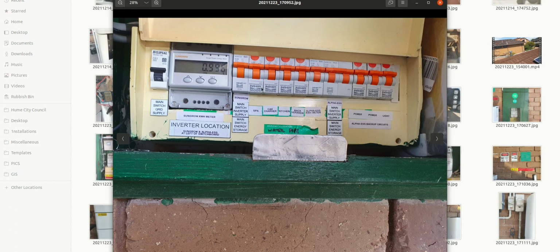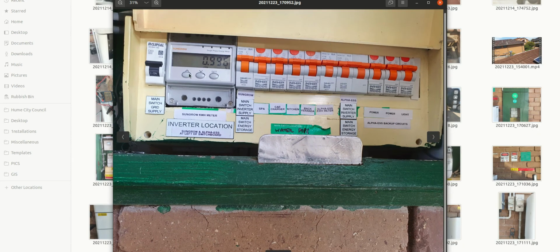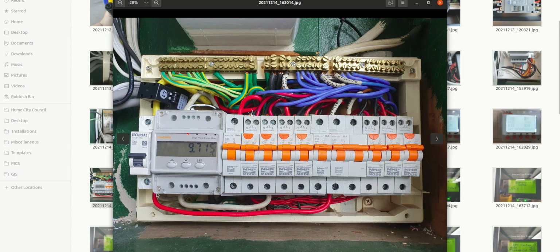These are grid connect. So when you had, yeah, that's right. This kilowatt hour meter here is grid side, and the Alpha ESS has its own backup circuits. And this kilowatt hour meter here from this retro system can't recognize any other system. So the answer was to, I have to rethink this. That's it, I can see a wire going around the back and up over the top before it goes into these grid connect side here, yeah.